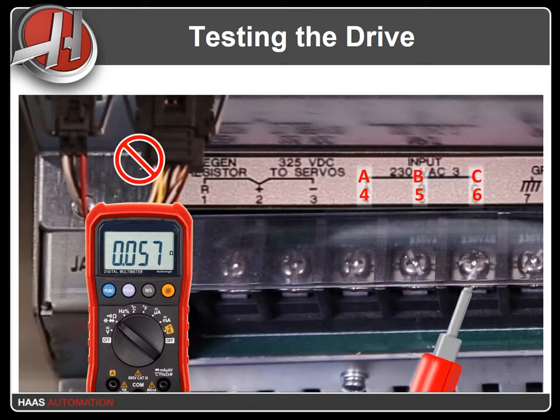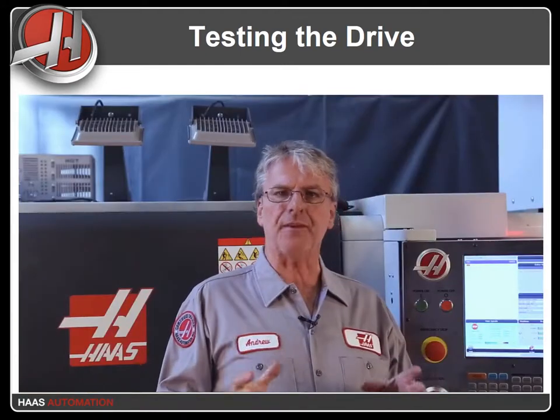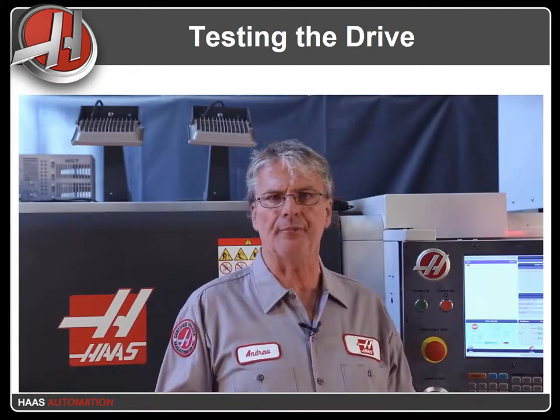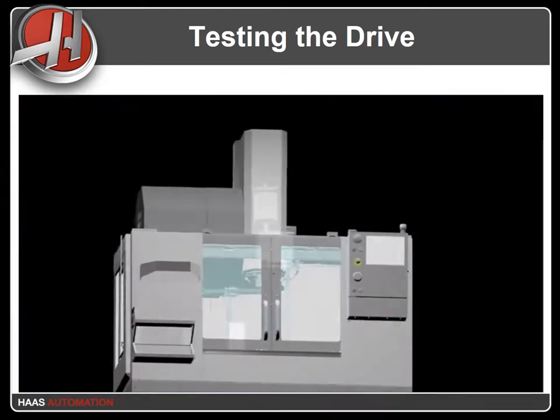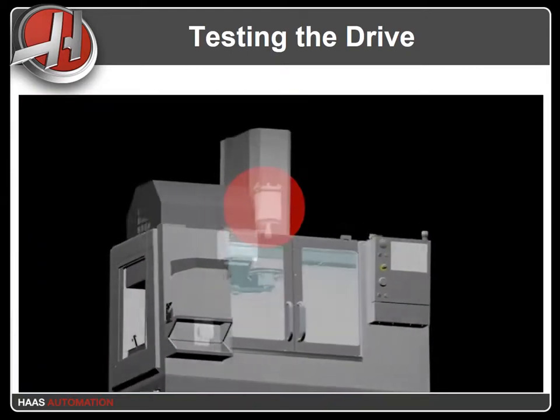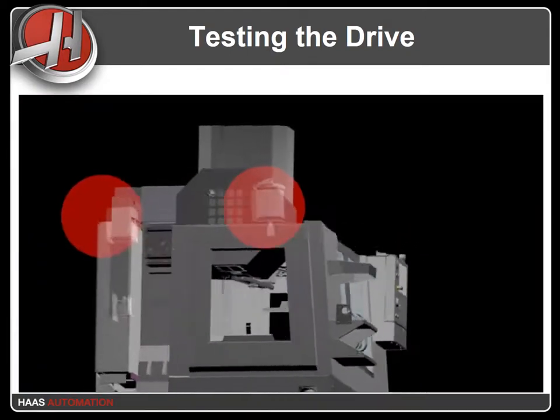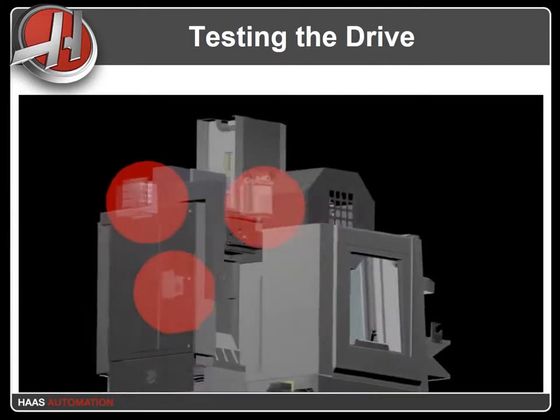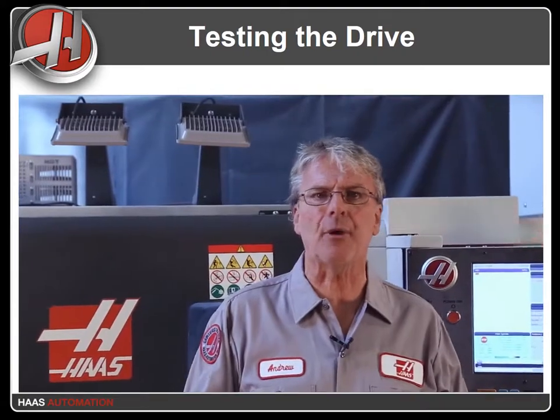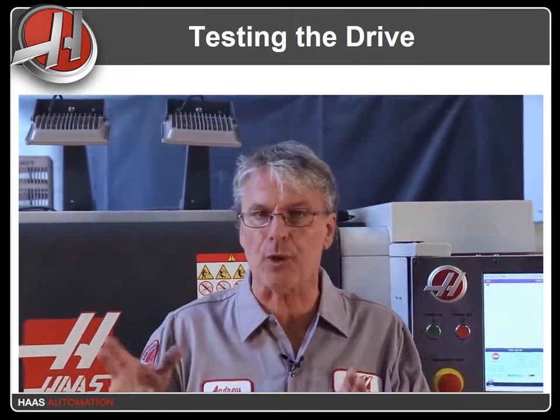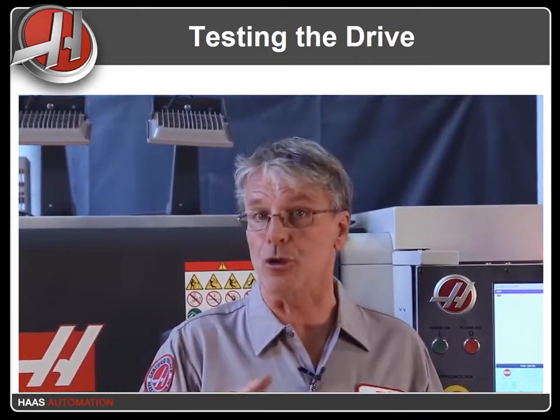Now that you've determined the vector drive has failed, it's important to eliminate other possible causes. Check the spindle motor, the spindle motor cables, the regen assembly, and the Delta-Y assembly if fitted, for shorts or for other damage. Make sure that you identify and repair any problems here before you replace the vector drive, or you just might damage the new one in the same way.